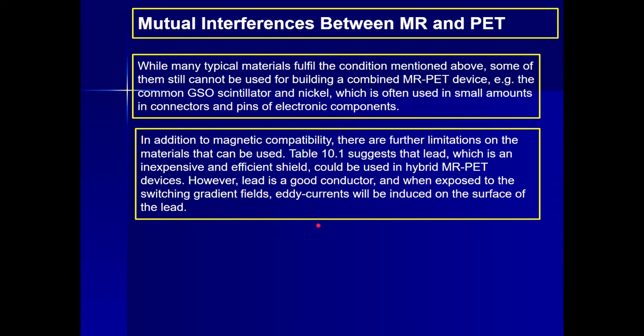In addition to magnetic compatibility, there are further limitations on the materials that can be used. Table 10.1 suggests that lead, which is an inexpensive and efficient shield, could be used in hybrid MR-PET devices. However, lead is a good conductor, and when exposed to the switching gradient fields, eddy currents will be induced on the surface of the lead.